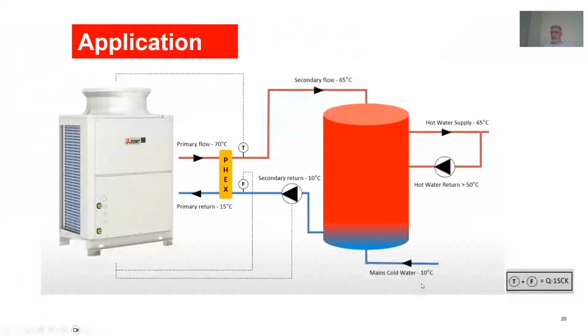How it generally works: you have cold city water coming in at the bottom of a tank, and you connect this storage tank to a heat exchanger through a pump. This pump circulates depending on the temperature you set, and it does a heat exchange from a primary source, that is a hot water generator or CO2 heat pump. You get a set temperature, let's say 65 degrees centigrade, which is used by the facility.